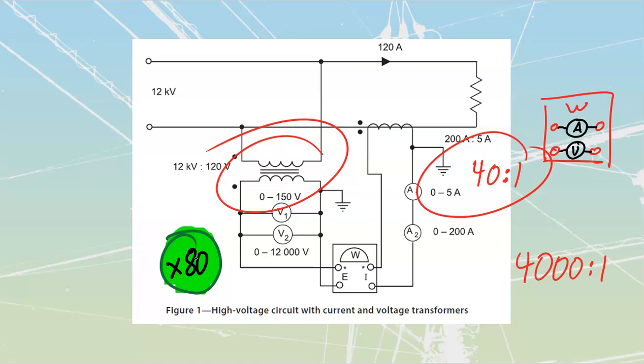I use the example of X80 because it's a common one in industry, but that is the watt meter multiplier. So whoever the meter reading technician is that's coming in there knows that they're supposed to multiply that by 80. Now, peeling the sticker off is not going to fool them. They know what's going on. If that sticker's missing, they'll look it up, or if it looks like it's been tampered with. But for you as an electrician, if you see an X something on the side of a meter, you can take whatever your reading is and multiply it by that, and that should give your meter reading.